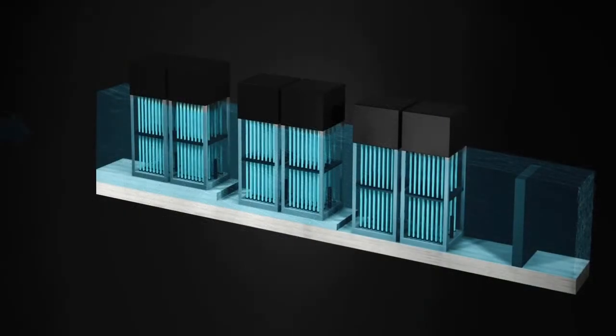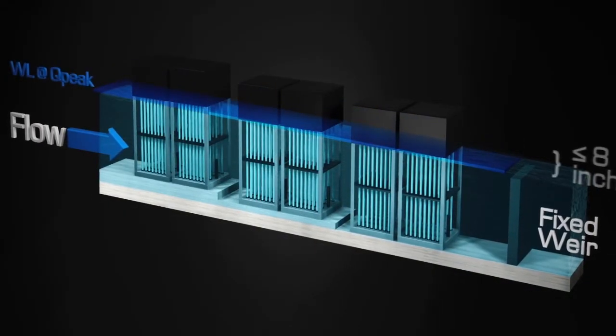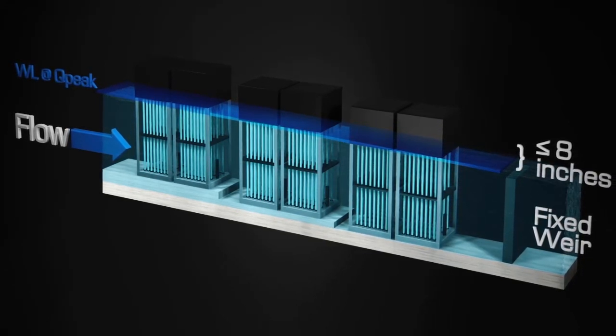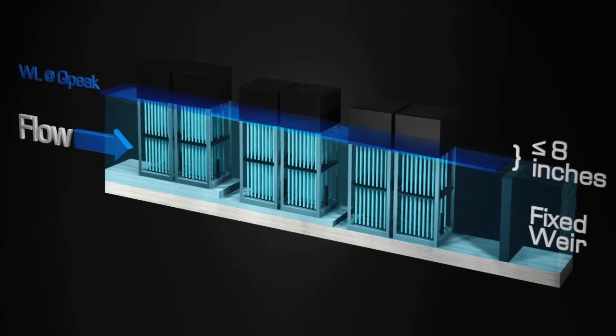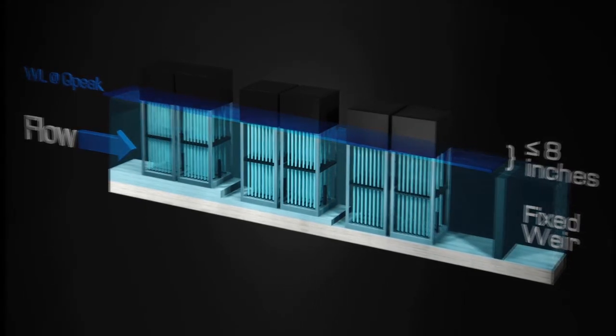Here is a traditional open channel vertical UV system with a stepped channel floor. The stepped floor is used to address the water level variance between low flow and peak flow conditions, and specifically to prevent flooding of the upstream lamps at peak flow.